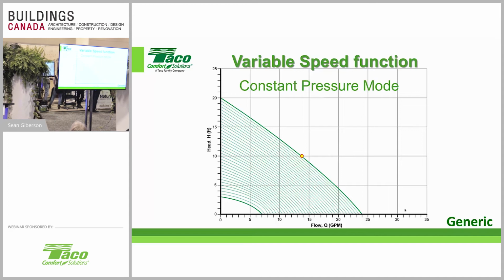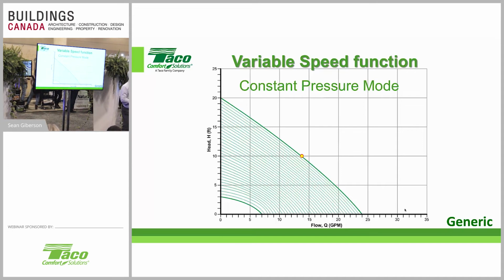Okay? What's going to happen, though, anytime we have a system change, we can create a new pump curve. In this case here, there could be like 40 pump curves. We're going to reposition the operating point on that circulator, okay, and how it works. So as soon as it sees a zone close, no need for sending energy there anymore, rather than ramp up and begin to push the efficiencies out, change that delta T we talked about in the beginning, rather than impact the delta T and the performance of that boiler generation equipment, now we just slowed down. So we didn't, in fact, impact that. Well, not adversely anyway. From a positive side, we slowed down the speed at which that product was moving water or fluid through the system. And it happens over and over and over.